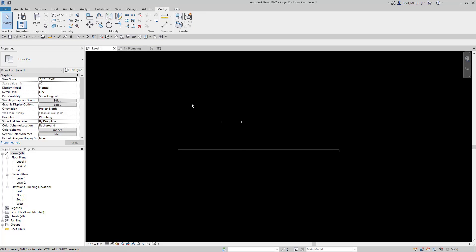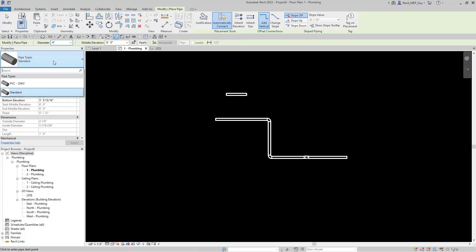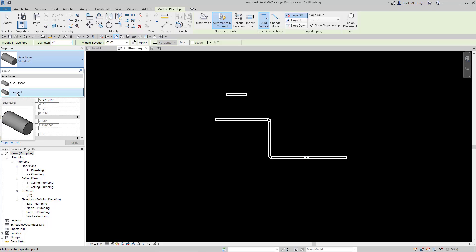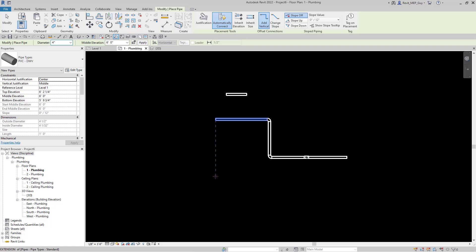So that is the easiest way to load in all of your fittings and all of your routing preferences without having to select each one. Anytime you don't have all of your fittings and don't have a pipe type that's working in your project, the easiest thing to do is open up the plumbing default template, draw a piece of pipe, copy that pipe, and paste it into any project that needs your pipe types and pipe fittings. Now, another great thing about the plumbing default template is that if we go to Systems and go to Pipe, you can see there are two types of pipe: Standard and PVC. Standard is going to be used for your domestic water, hot water, or any generic piping, and PVC should be used for drainage piping — sanitary or storm.